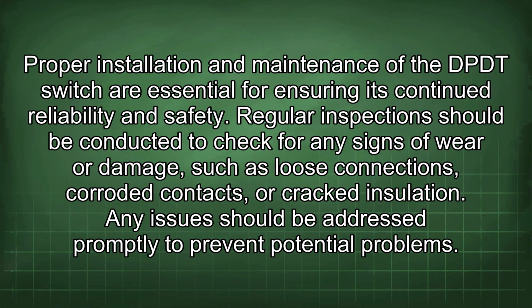Proper installation and maintenance of the DPDT switch are essential for ensuring its continued reliability and safety. Regular inspections should be conducted to check for any signs of wear or damage, such as loose connections, corroded contacts, or cracked insulation. Any issues should be addressed promptly to prevent potential problems.